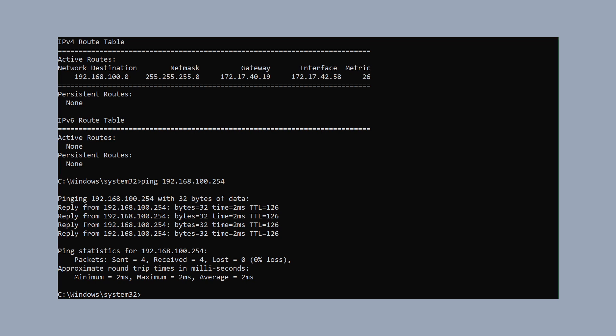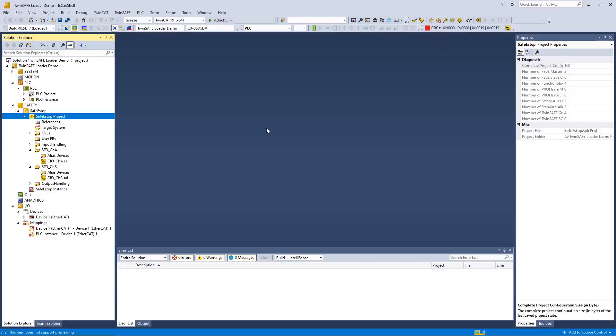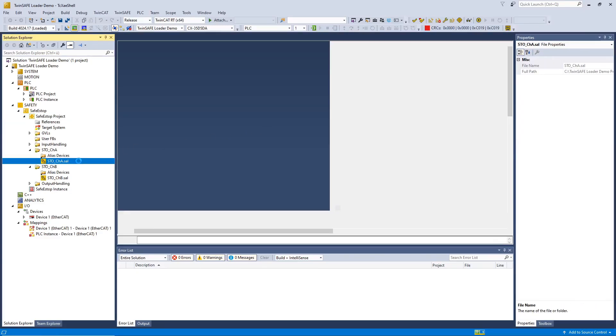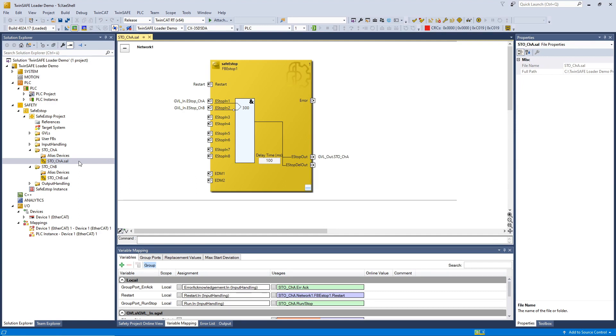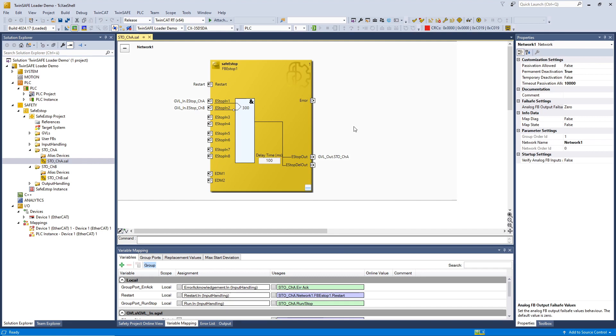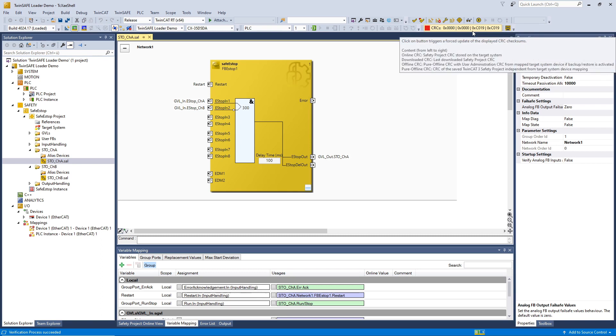We can now ping the gateway and everything works fine, so we should be able to use the TwinSAFE Loader. In the next step, we prepare our safety project. As we want to also show you the customizing functionality in the next tutorial, we have prepared our safety project for the customizing case. We have an existing TwinCAT 3 solution with a safety project, and for the customizing we want the TwinSAFE group STO channel A to be deactivatable permanently. In the TwinSAFE group configuration, we switch the permanent deactivation trigger to true.